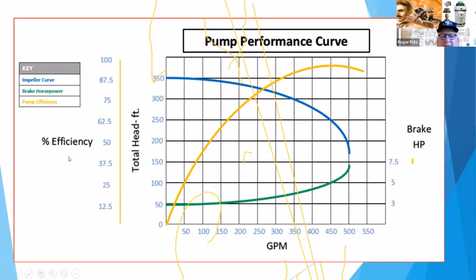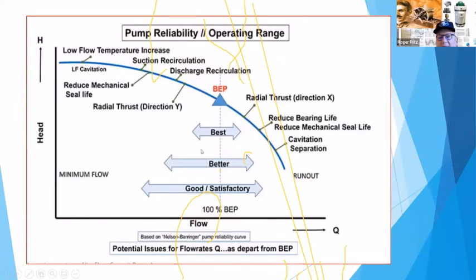Our whole world likes to operate in balance. You have a balance in operation, and keep it in its best spot, and then this is satisfactory. But you can see cavitation, run out, reduced bearing life, seals, all that. It affects the reliability of that motor and definitely the reliability of the pump.